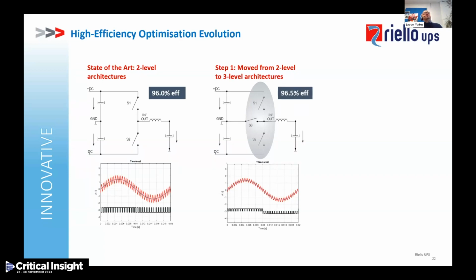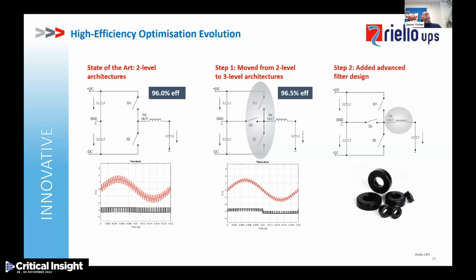The downside to three-level architecture is it requires more components and more processing power. So unfortunately, the three-level architecture traditionally would only be seen in larger UPS systems, say 200, 300, 400 kVA and above. But nowadays, you will see this technology in UPS systems as small as 10 kVA because processors have become more powerful and designing these systems has become easier and more compact. The next phase of evolution was to improve the design of the filter components. By improving the design of the filter components, it enabled us to push our efficiency levels up to around 97%. So we're getting somewhere closer now.